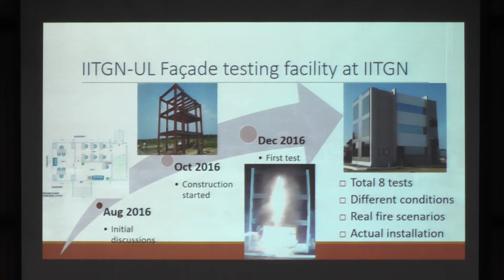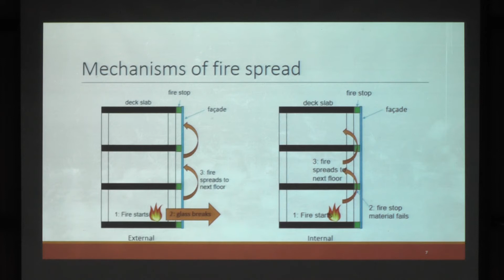Primarily, there are 2 mechanisms through which fire can spread from one compartment to the other. One is that if let's say fire starts here, then the glass of the facade will break and it will spread from outside. This kind of mechanism is called the leapfrog effect. The other is that the glass will not break, but the gap between the slab and the facade will give away, and the fire will spread internally. So this fire will not be visible from outside, but from inside it will spread.